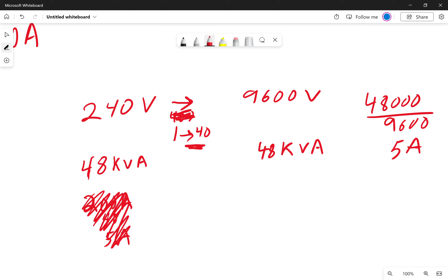I know my ratio is 1 to 40, so if I know the amperage on the primary side, I can divide by that ratio to get 5 amps. Or, if I haven't worked that part yet, since I know there's 48 kVA on the primary side, there's also 48 kVA on the secondary side, so I can divide that 48 kVA by the total number of volts on the secondary side.